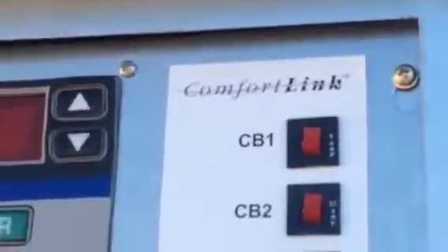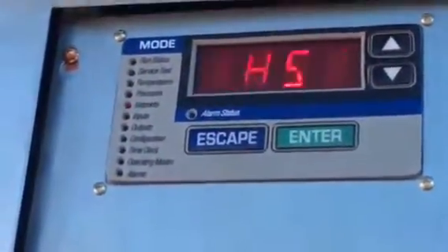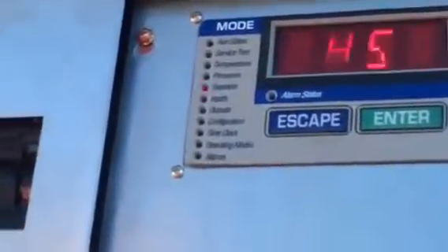So cooling mode, or the ability to start mechanical cooling, is based on a couple of numbers that are added to this occupied heating set point, which is by default 68. So with all default values, cooling is enabled on this one from 72 degrees and up. But now it's going to make its other decisions. Things such as, if I started a compressor and I shot to 45-degree leaving air with only one compressor, I'm going to hold it off before it starts again.